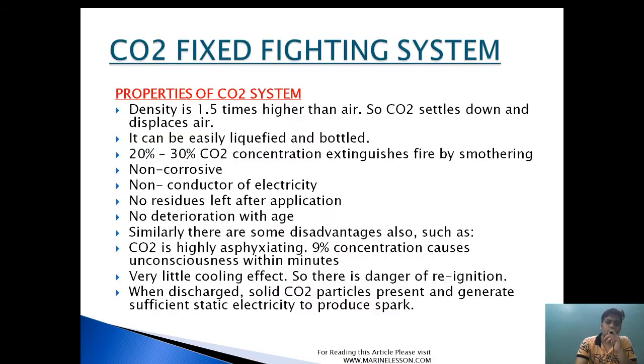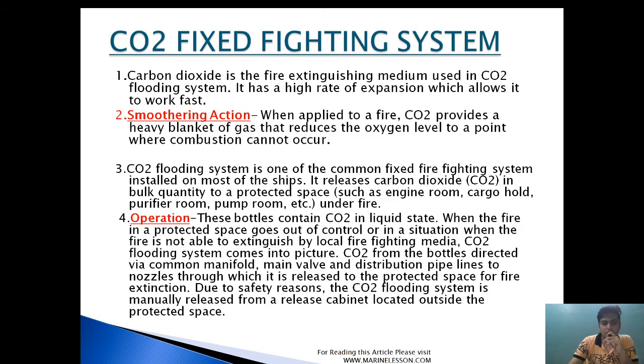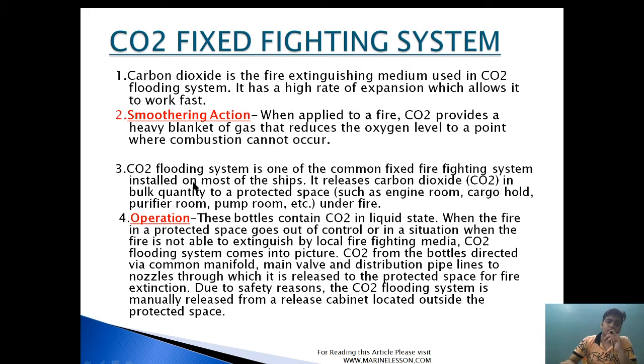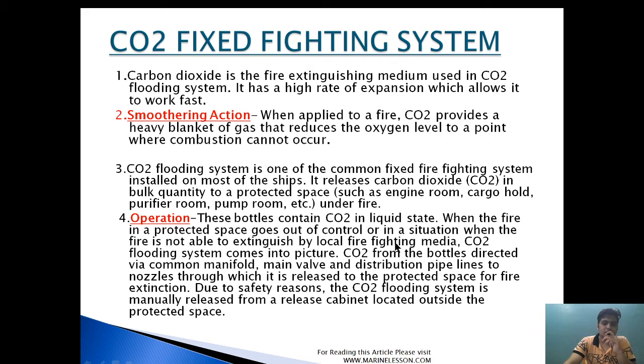In synopsis: CO2 fights fire by smothering action. CO2 is heavier than air — 1.4 times — and hence it reduces oxygen to a point where combustion cannot occur. CO2 is installed on a ship and can be applied in bulk quantity to areas such as engine room, cargo hold, purifier room, and pump room. You can watch the video on CO2 fixed installation Part 1 for the full system explanation.